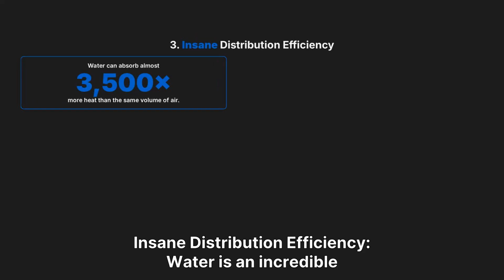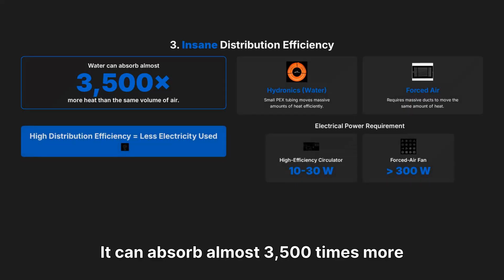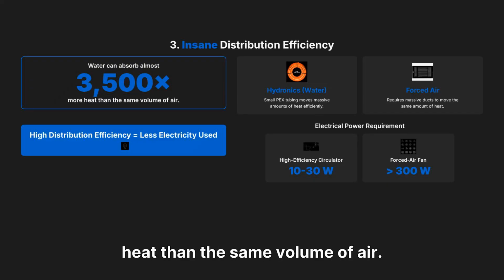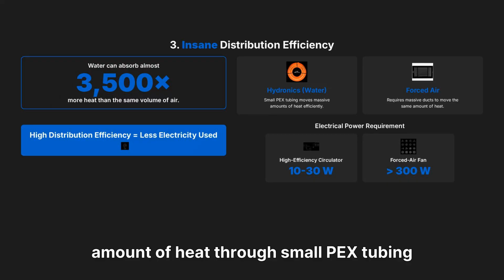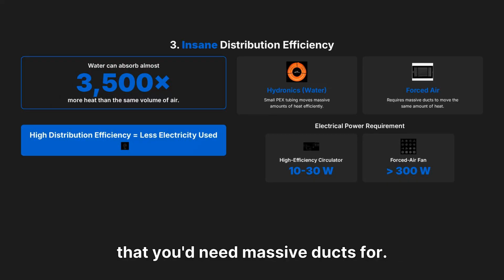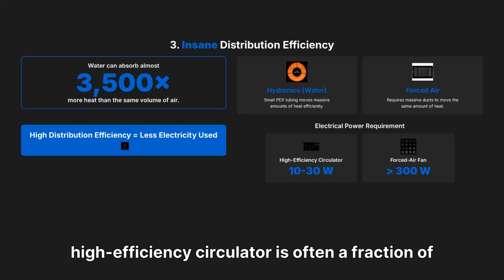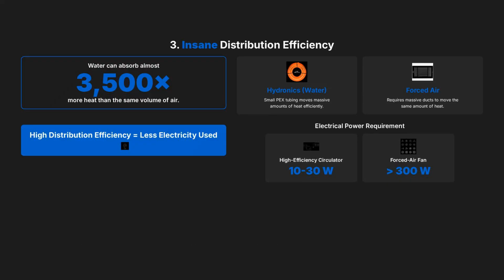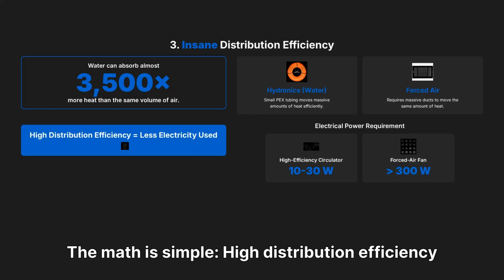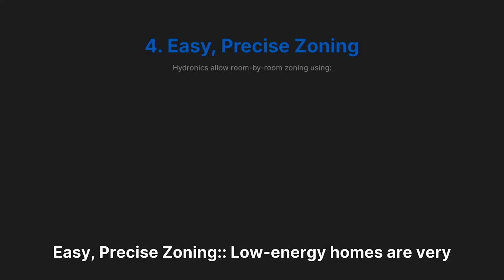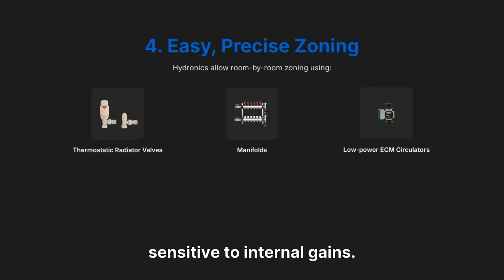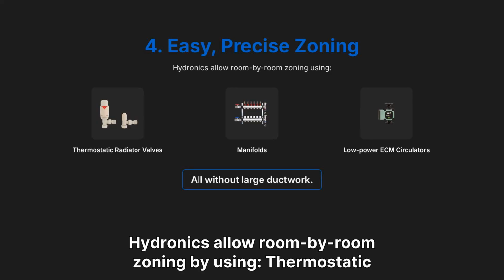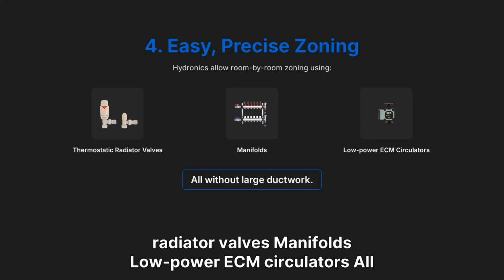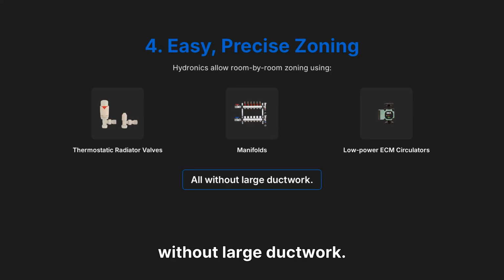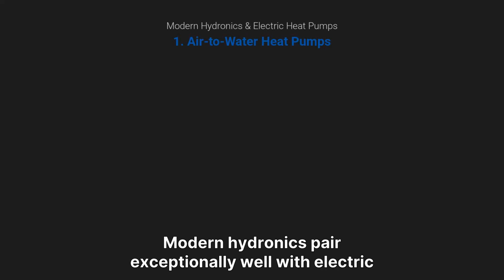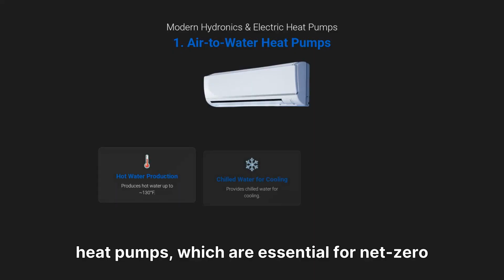Third, insane distribution efficiency. Water is an incredible heat conveyor. It can absorb almost 3,500 times more heat than the same volume of air. This means you can move the same amount of heat through small PEX tubing that you'd need massive ducts for. The electrical power needed to run a high-efficiency circulator is often a fraction of what a forced air fan requires. The math is simple. High distribution efficiency equals less electricity used. Fourth, easy, precise zoning. Low-energy homes are very sensitive to internal gains. Hydronics allow room-by-room zoning by using thermostatic radiator valves, manifolds, and low-power ECM circulators, all without large ductwork. Modern hydronics pair exceptionally well with electric heat pumps, which are essential for net zero buildings.